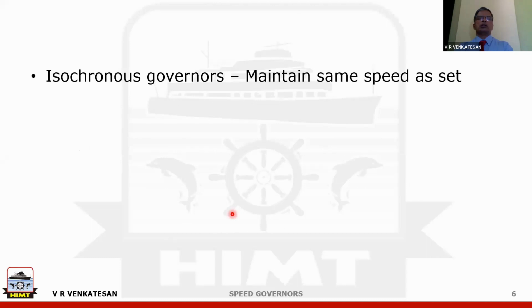As far as speed control is concerned, there are two types of governors. One is called an isochronous governor. In an isochronous governor, the speed will be maintained at the set speed. That means if the load changes, if more kilowatt or less kilowatt is drawn from the prime mover, the speed will be maintained the same. That is called isochronous. When we say speed is maintained the same, it does not mean speed will not change at all. In any kind of control application, whenever there is a disturbance, the value will change, but it will recover back.